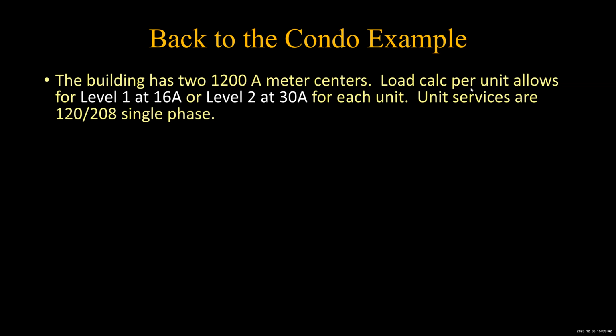But if you try to add to that, you can't add very much, because the diversified load at 23% gets you pretty close. And it may not be 30, whatever the number is. So you still have to add, and you're designing the building. Yeah, my recommendation on that is work it out. Either you have to put in probably larger meter banks than you otherwise would. But if you're talking about the condo service itself, then you're talking about what we've just gone through in the calculations.